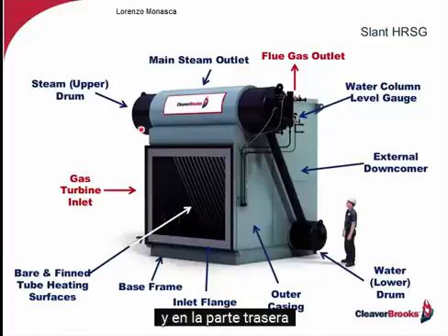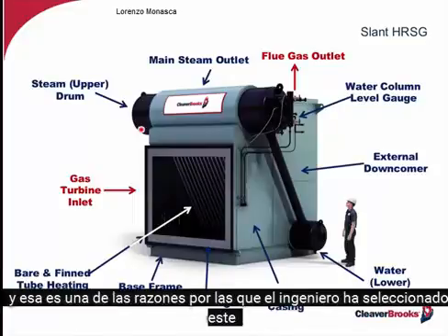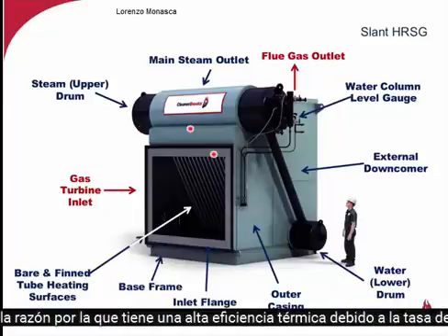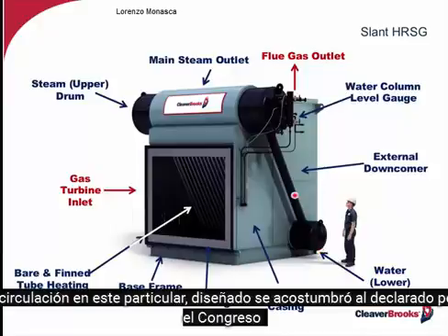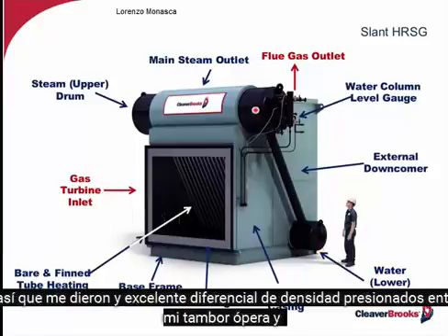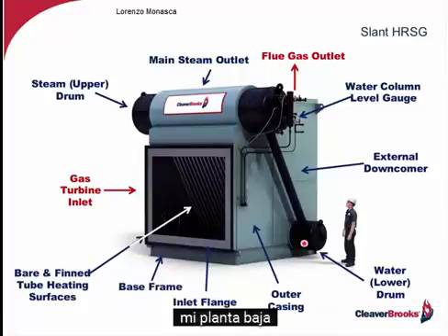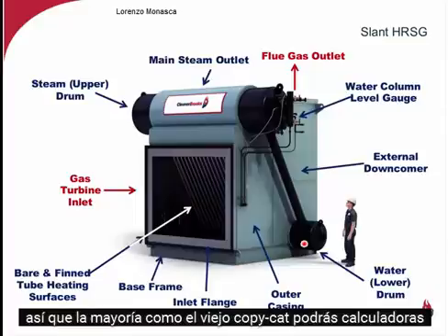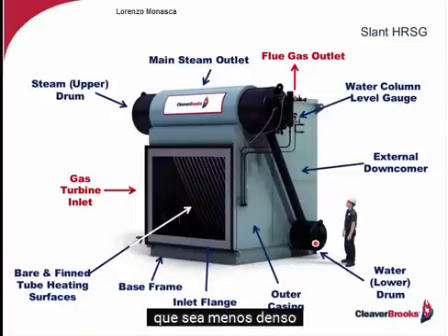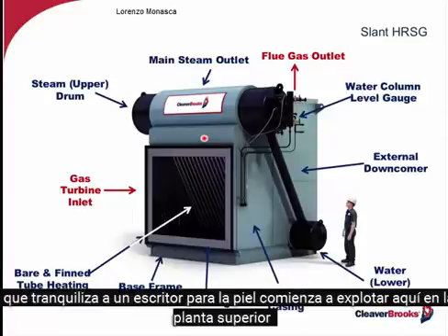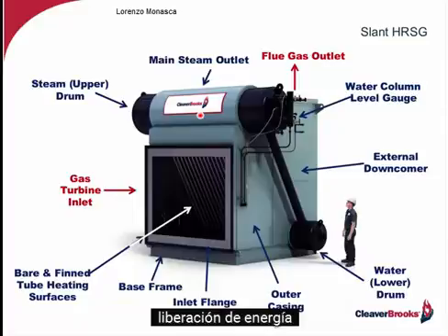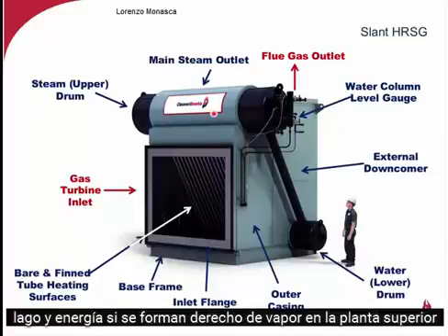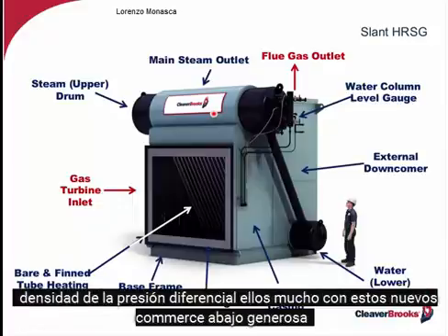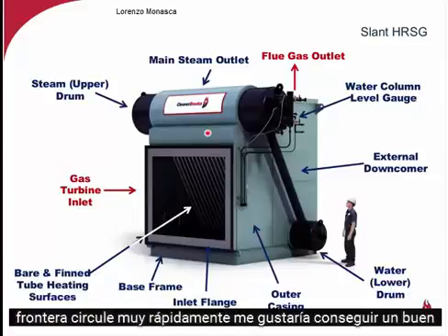Now, it also has a high thermal efficiency, and that's one of the reasons why the engineer has selected this. The reason is the rate of circulation in this particular design. It's got these isolated downcomers, so I've got an excellent pressure density differential between my upper drum and my lower drum. It's almost like the old coffee percolators: once the water was heated, being less dense, it finds the riser tubes and begins to explode up into the upper drum and release its latent energy, forming steam at the upper drum. This pressure density differential, with these generous downcomers isolated, allows this boiler to circulate very, very rapidly.